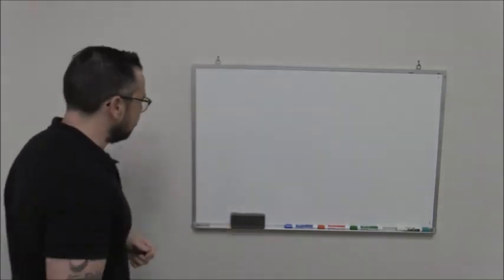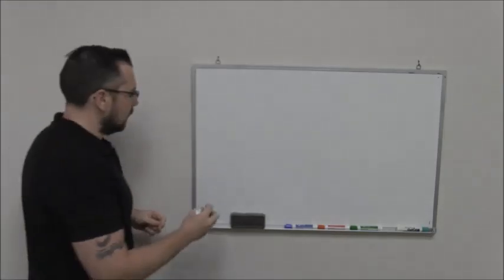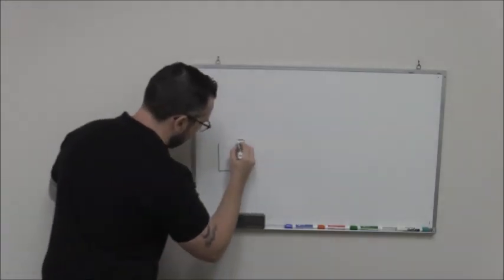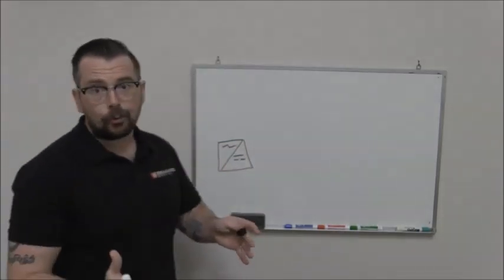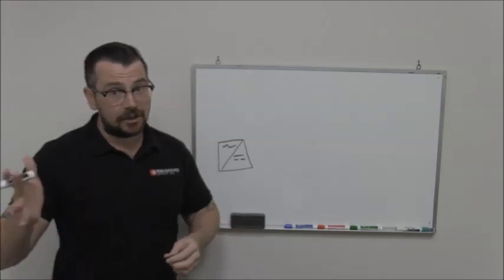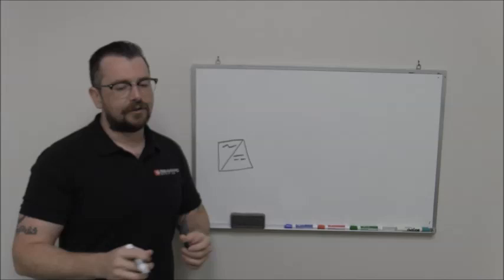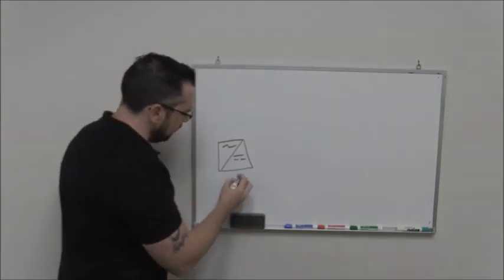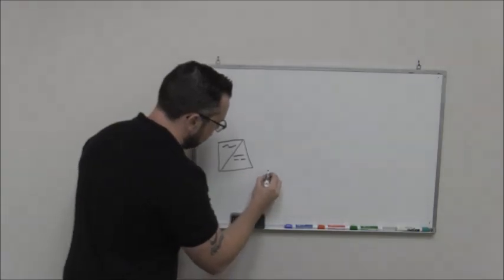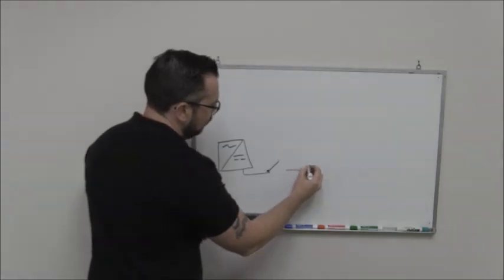So first of all, if we look at the typical layout of a PV array, we can apply this to residential, commercial, even utility-scale plants. First we're going to have an inverter somewhere, and then from the inverter we're either going to have maybe, in Europe we call them a DC isolator, here in the States it's a DC disconnect. That might be underneath the inverter or to the side, and then also we may have a junction box.